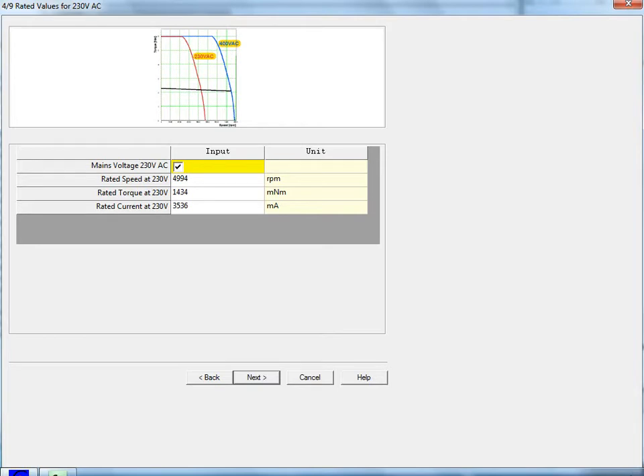Steps 4, 5, and 6 are for the motor's current, torque, and speed at 230, 460 volts AC. The speed limit is in RPM, the torque is in milli-newton meters, and the current is in milliamps. Again, current is at amps RMS per phase. If the motor is not rated for the higher voltage, leave those unchecked.